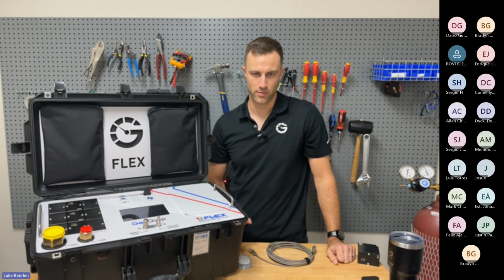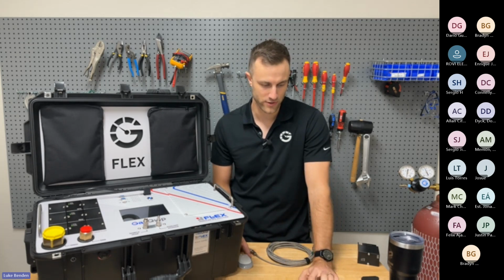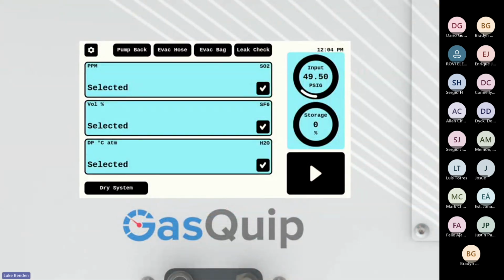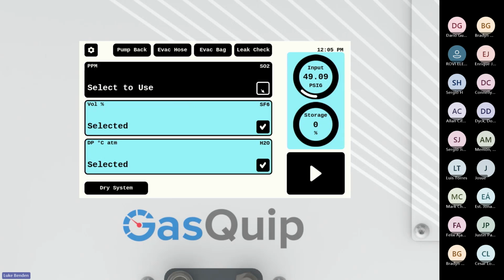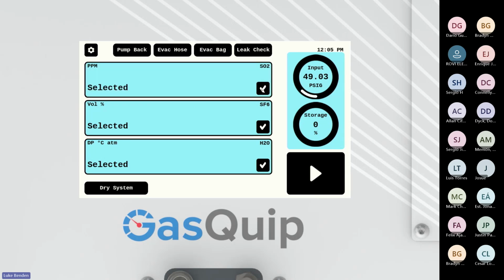We can now talk about the operation and show you what the analyzer looks like up close. This is the up close live feed of the analyzer. Hopefully you can see my mouse okay. This is what the device looks like whenever you turn it on. I'll go over the different areas. In this big area, you have the different sensor modules that will be plugged in at that time. Up in the top left, you have the units. The top right has the name of the sensor module, in this instance the SO2. Then it'll say selected, and if you deselect that, it'll say select to use.